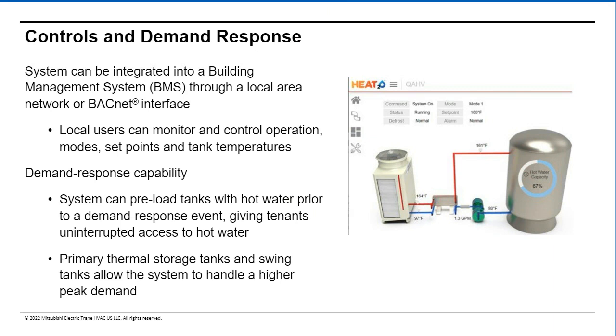The system can be integrated into a building management system, BMS, BAS, through a local area network or BACnet interface. Local users can monitor and control operation, modes, set points, and tank temperatures. There is demand response capability. Systems can preload tanks with hot water prior to a demand response event, giving tenants uninterrupted access to hot water. Primary thermal storage tanks and swing tanks allow the system to handle a higher peak demand.